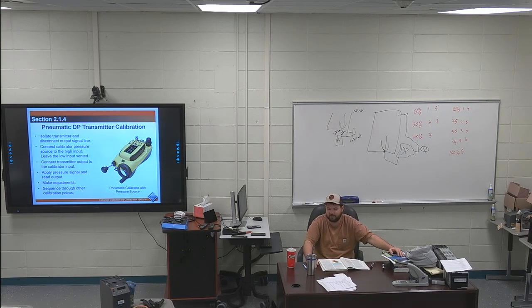Like a lot of times, like in plants and stuff, you're working on something here, and then you have to go to the control room, 100 yards away, to go calibrate it. So either you've got to have a partner with radios, or you can actually set up one of these to do a step function. You can go in there and say, like, for some reason the 50% point is like 10 degrees off or something like that. Like it'll step through those for you. Like you just push a button and it'll start doing the different steps.